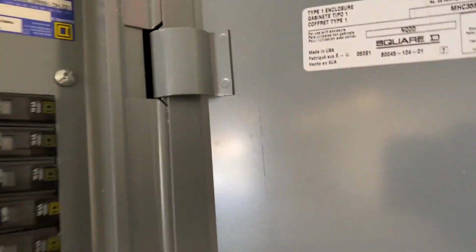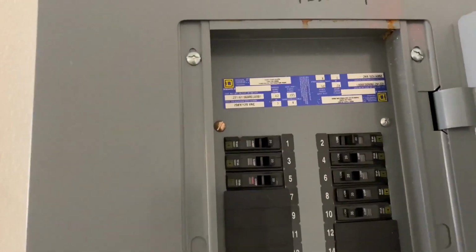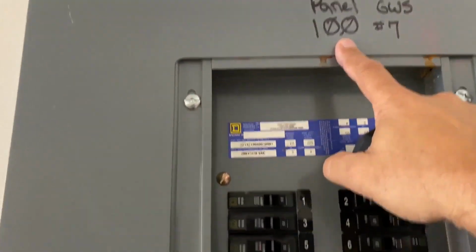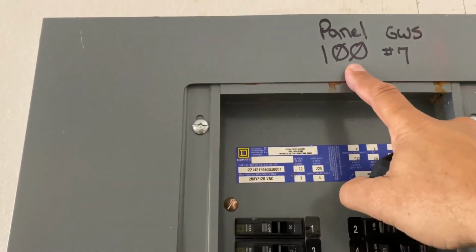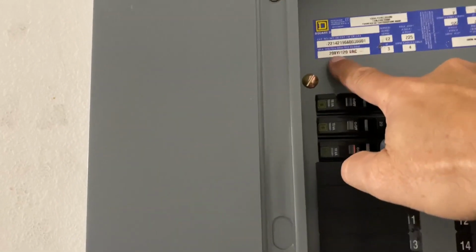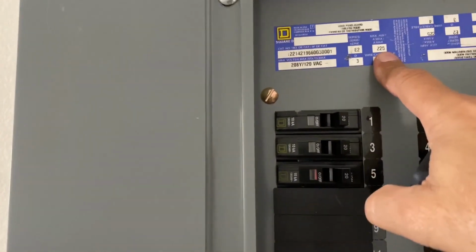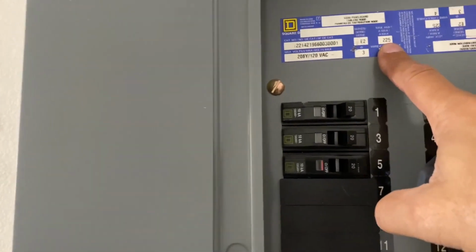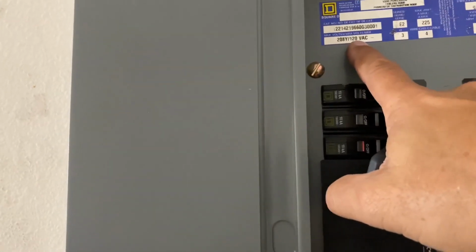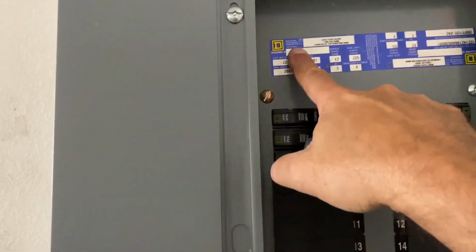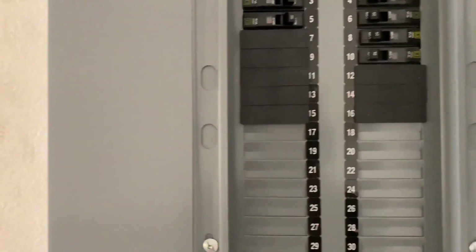So basically, sometimes you get old panels that need to be replaced. This is not that old of a panel. They're calling it 100, which corresponds probably to the meter cabinet, that this is suite 100. This shows you that it's a 200 amp. It's going to say 225, but that's a 200 amp panel. 208, 120 volt, 3-phase, 4-wire. So I look for that. Square D is a common brand. Those are really the basics.